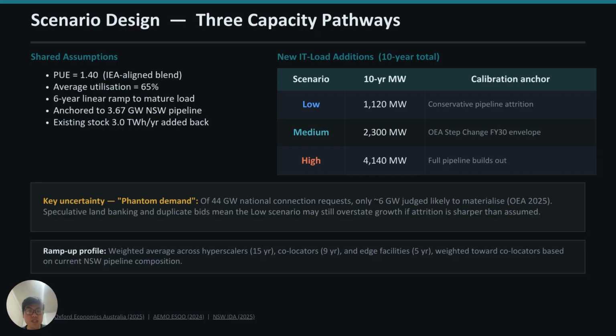So we developed three scenarios, low, medium, and high, by varying the schedule of new IT load additions against that pipeline. All three share the same technical assumptions: a PUE of 1.40, average utilization of 65%, and a 6-year linear ramp to the mature load.